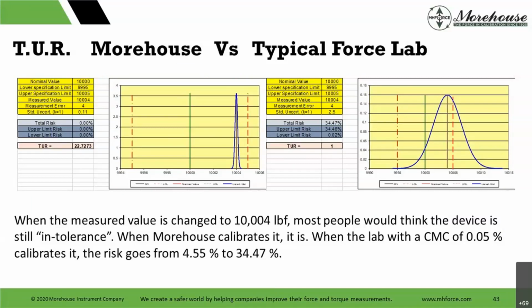It's basically because if Morehouse or somebody else tells you that to generate 10,000 pounds of force, load it to 10,004, and if you're consistently doing that, that changes things. But general industry doesn't do that. General industry basically says, I have this device, I'm going to load it to 10,000 pounds of force, and I'm going to call it 10,000 pounds. I'm not going to say it read 10,004. I'm not going to use a curve or an adjustment to bring it back in.